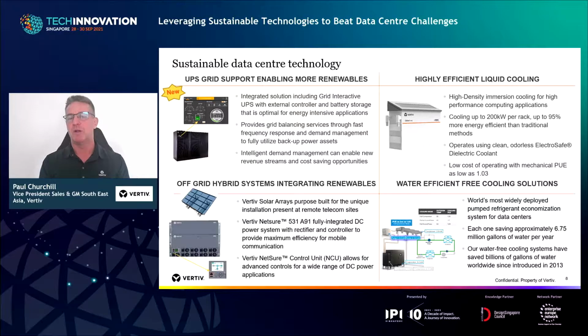One of the trends and technologies we're looking at more and more is high density immersion cooling. As data centers expand, we're looking at increasing the density of each rack within a data center. Previously, I'd say 10 years ago, it was 2 to 5 kilowatts per rack. For many years we've talked about density increasing, particularly with blade servers and things like that coming on board, but we never really saw those high density solutions appearing in data centers as expected.